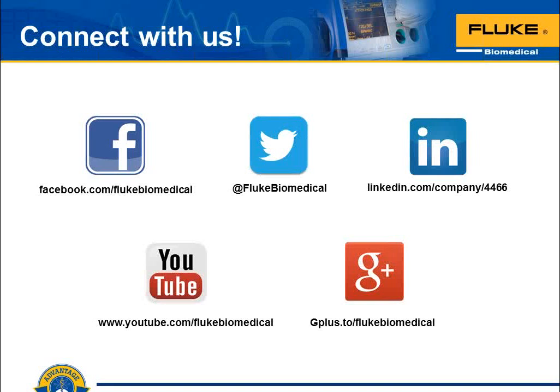But indeed it does, because here's what Valley Lab says in the service manual for LigaSure. They say, if bipolar, cut, and coag are within tolerance, LigaSure is within tolerance, and there's really no test. So my answer to this is, yes, of course it does, based on the information from the manufacturer of models of ESUs that include LigaSure.